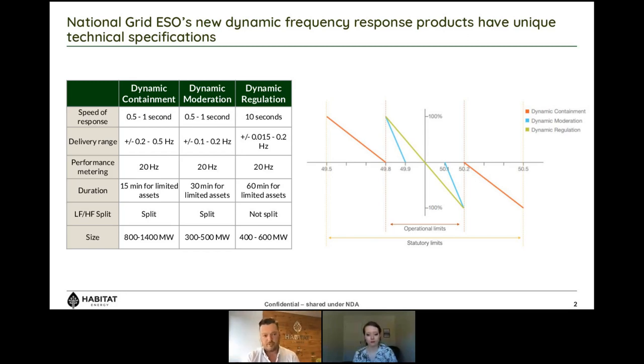There's also the concept of duration-limited assets. If you're bidding into these services with a storage asset that can't continue providing service indefinitely, what is the minimum duration required? For dynamic containment it's 15 minutes. For dynamic moderation and dynamic regulation, National Grid's current view is 30 minutes and 60 minutes respectively — though conversations are still ongoing to fully define DM and DR, but that's where their minded-to position is.